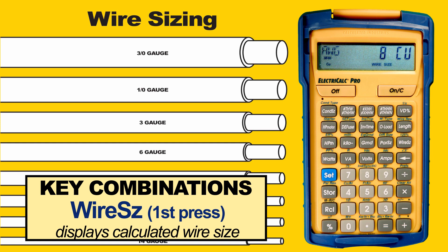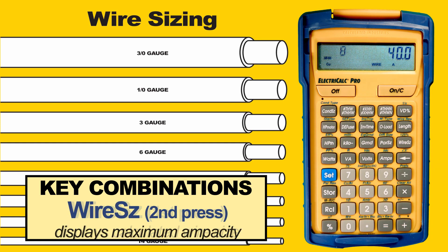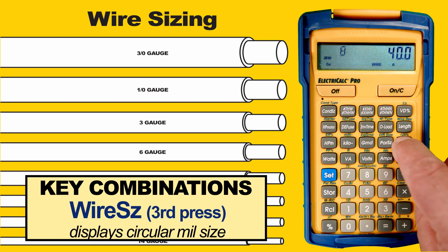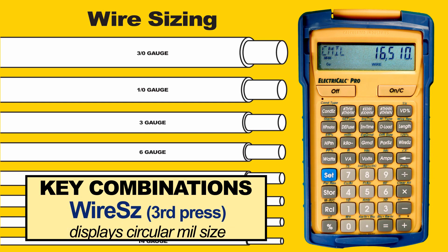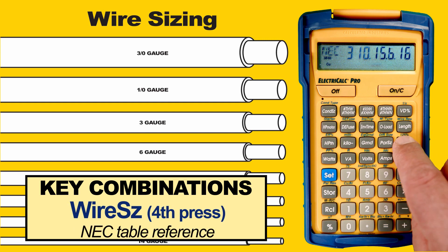It tells us that we will need an AWG number eight size copper wire based on these entries. Press Wire Size again and it displays the maximum ampacity that conductor wire size can carry based on the code rating. Press it again and you will see the circular mil size of that wire. The final press displays the table reference where the information came from.